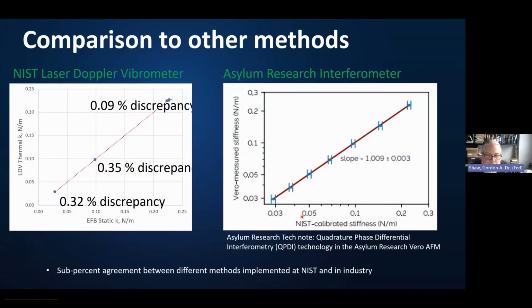So we've done this for a subset of the cantilever devices, and we compare that against other methods. So in NIST, there's a laser Doppler vibrometer method that measures the thermomechanical vibrations of the AFM cantilever to calibrate, to measure a spring constant. And our two methods agree within 1%. Also in industry, Asylum Research has measured the spring constant of our AFM cantilever reference material using their quadrature phase differential interferometer. And that agrees also within 1%.